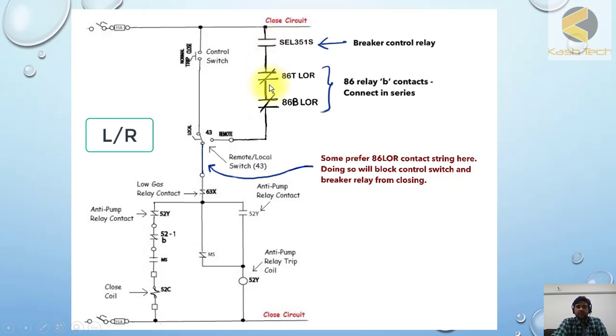And it will be going through both lockout relays. If any lockout is operated, then closing will not happen. These are interlocking checking. After that, it will come down further. Then low gas relay will check that SF6 pressure is okay in the breaker.